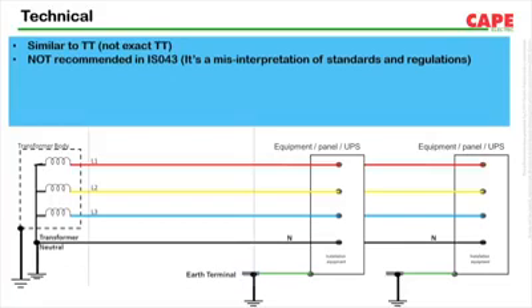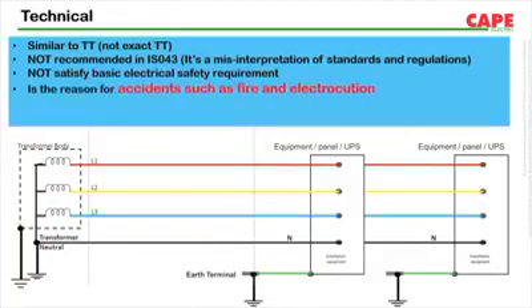These kinds of earth connections are due to misinterpretation of the standard. This kind of connection is the reason for accidents such as fire and electrocution, because automatic disconnection of supply will not function properly during an earth fault. Often earth electrodes in soil are interconnected under soil as a ring or a grid, which will bring additional problems for electronics and will create problems for the functional safety equipment.